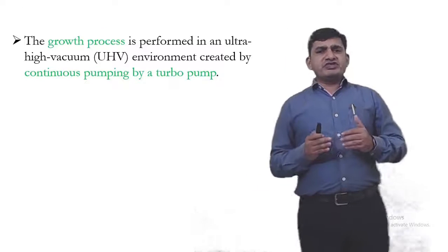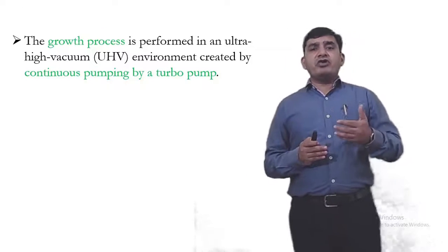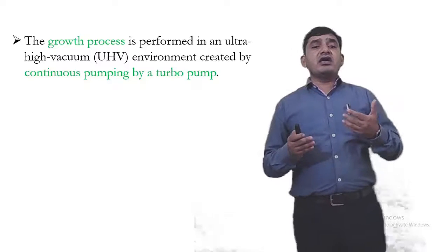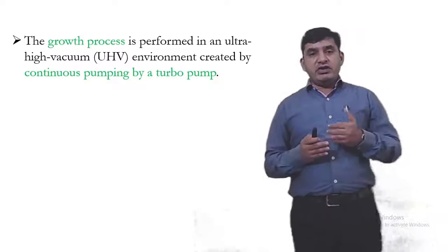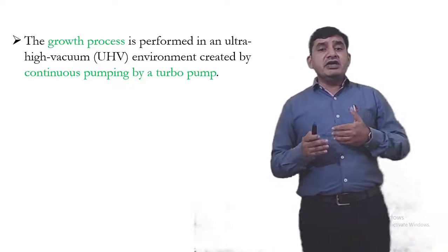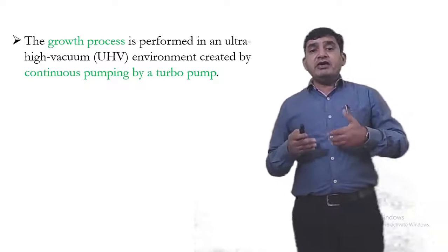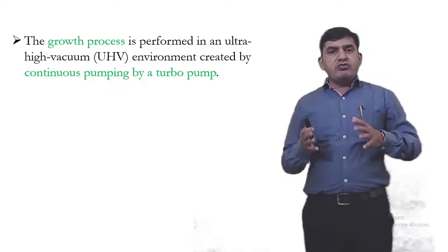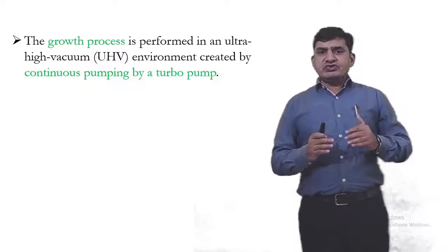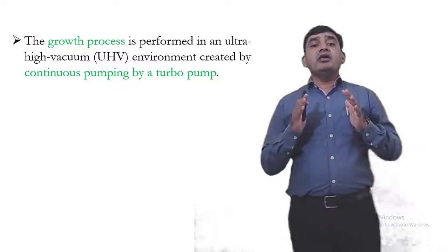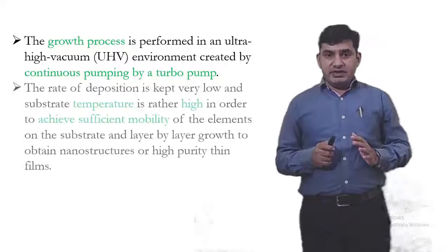The growth process is performed in an ultra high vacuum environment created by continuous pumping by a turbo pump. We use the turbo pump to create a high vacuum environment.